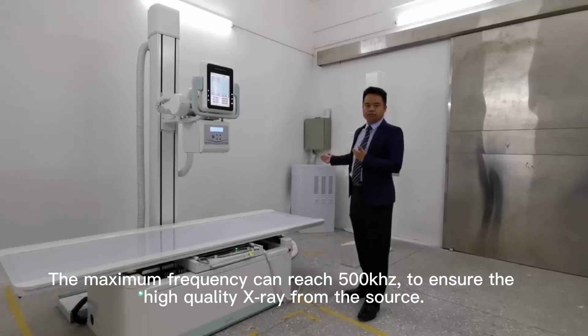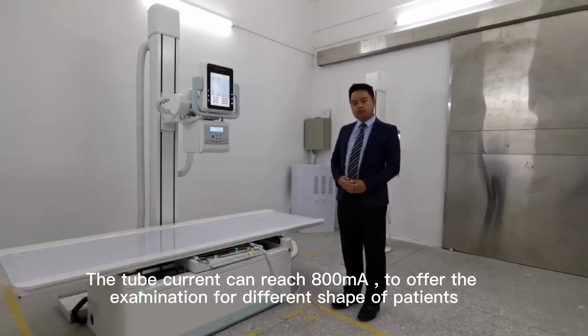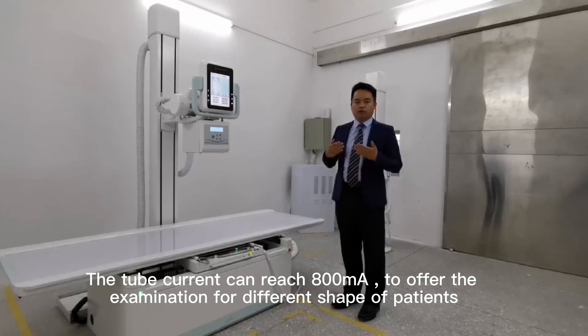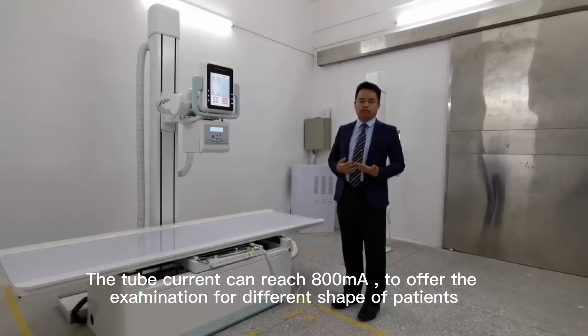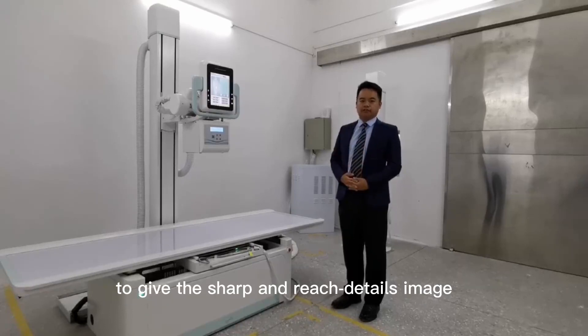The maximum frequency can reach 500 kHz to ensure high-quality imaging from the source. The tube current can reach 800 mA to enable diagnostics for patients of varying size. The tube voltage can reach 150 kV. It can perform high-quality examination for the chest using sharp and clear imaging.